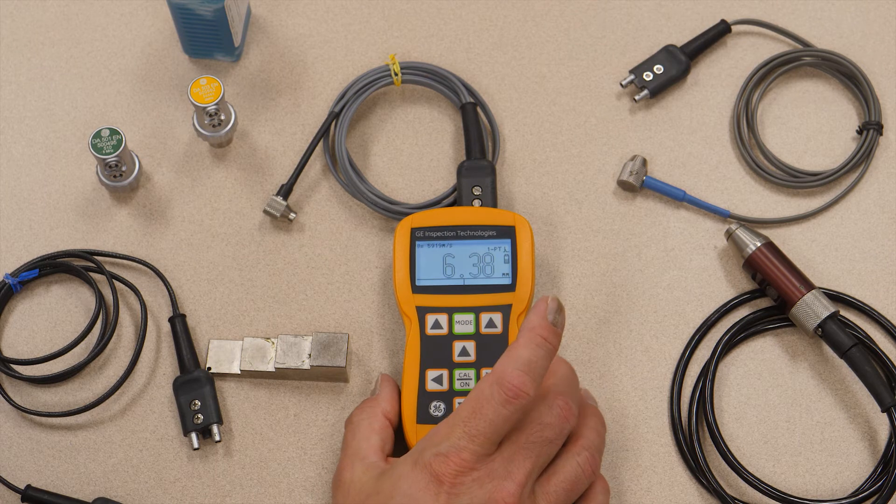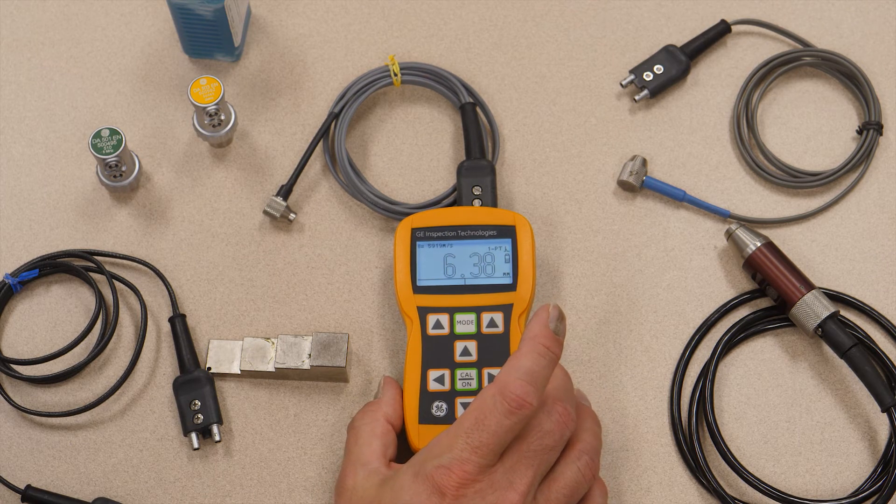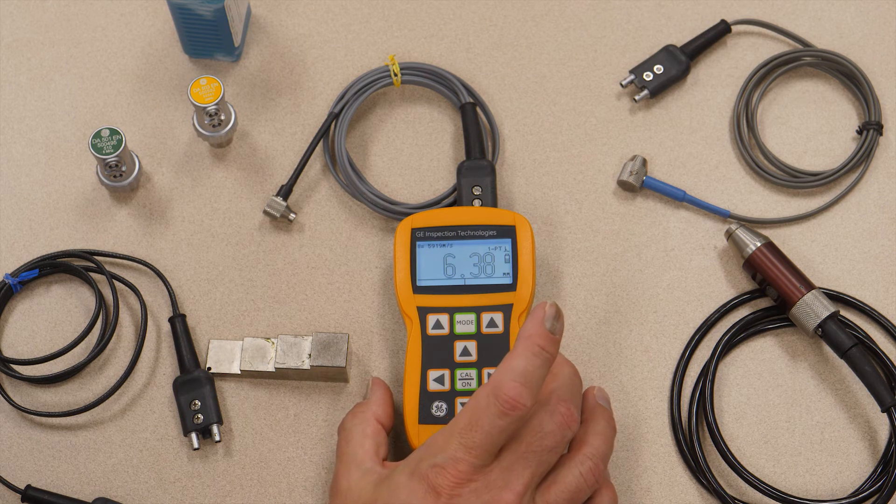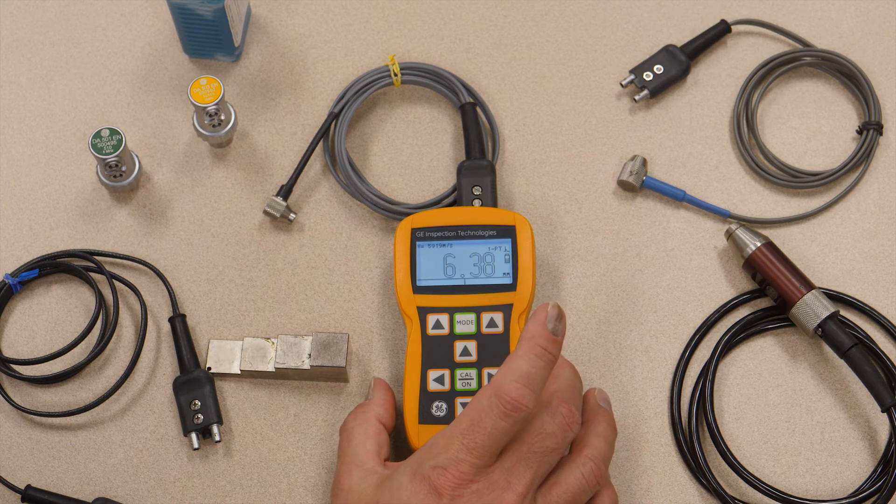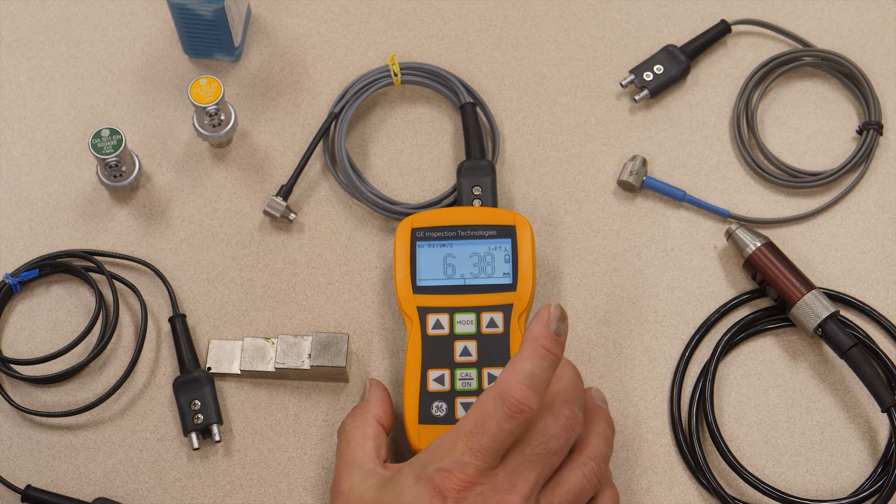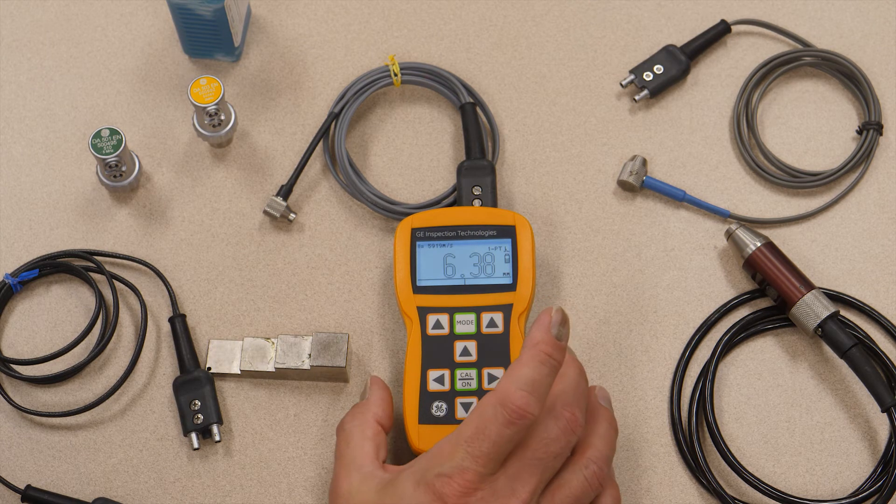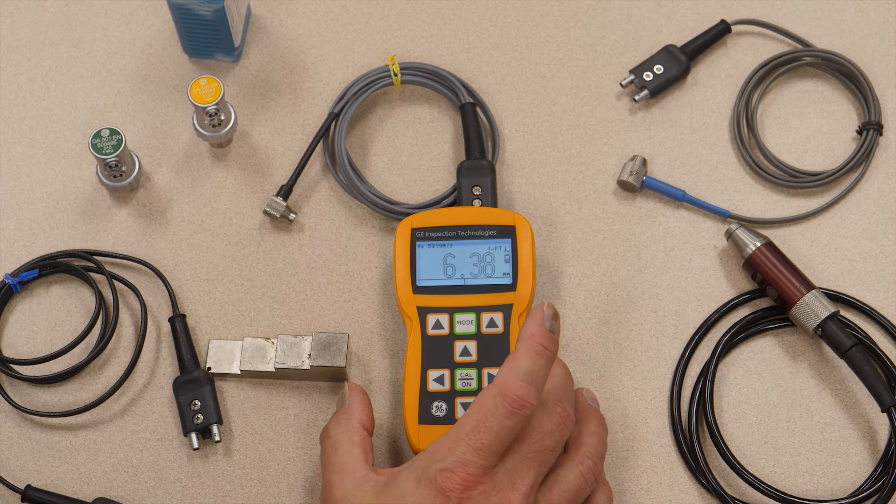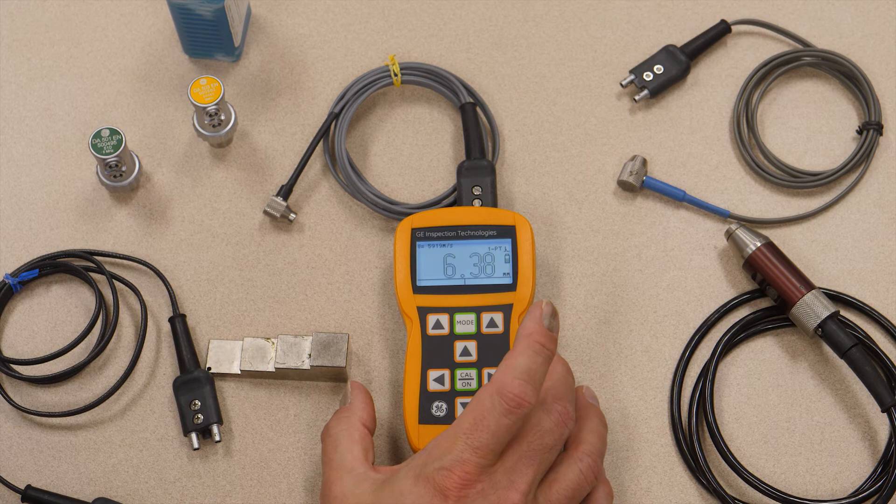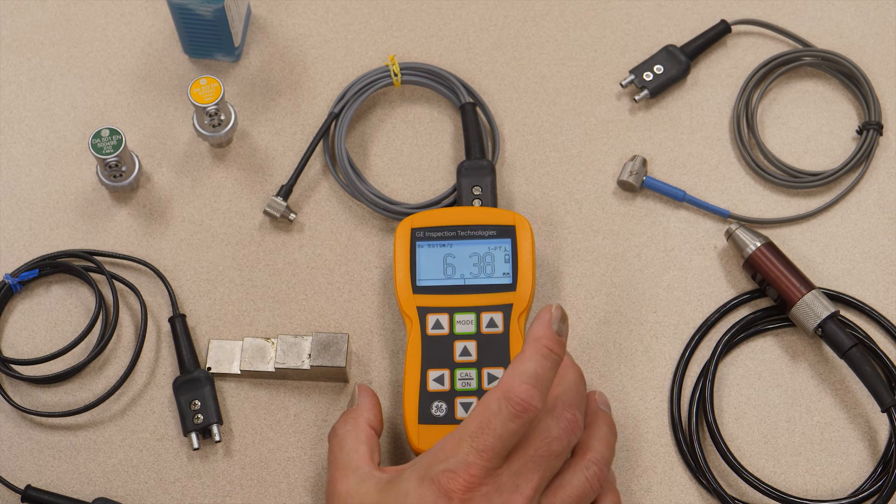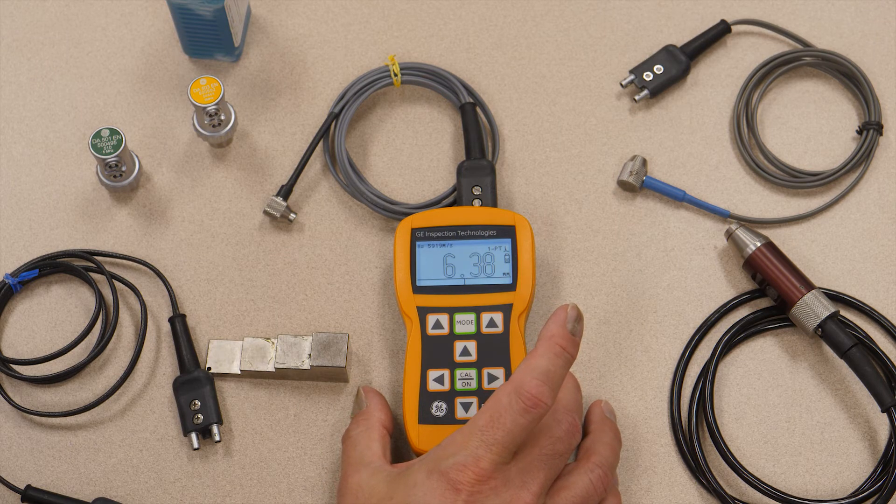The other option that's available in this instrument is dual multi-mode, which provides the capability to take measurements through coatings. So if you have painted material or epoxy coatings on material, you can easily take thickness readings through those coatings. However, the coating thickness in normal dual mode will be added to the thickness of the base steel, so it's going to throw your reading off.